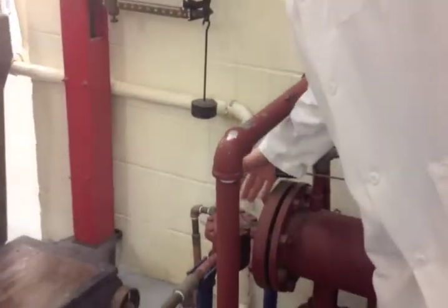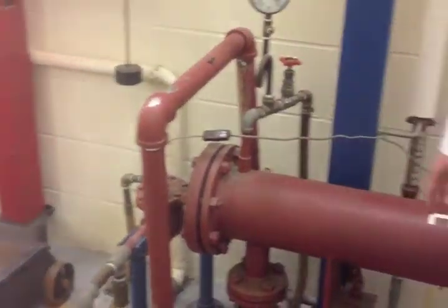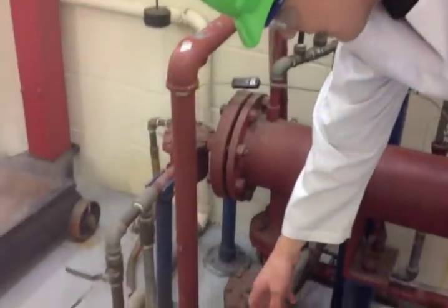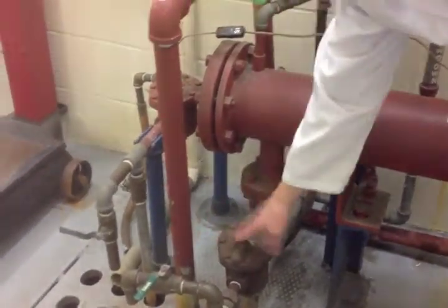Finally, we need to look at the steam outlet, so we can come all the way down here to 15 and measure that. But steam's a little tricky because the temperature really should be above 100 the whole time. We're trying to keep the steam saturated. So what we do instead is we can measure the temperature of the water coming out of our steam trap.